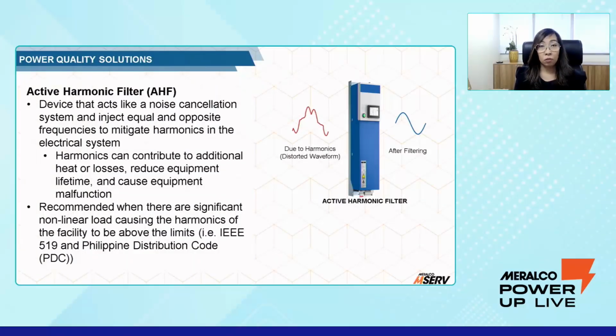So what are these solutions? First up, we have an active harmonic filter. This is by ComSys, the world's leading active harmonic filter manufacturer. It acts like a noise cancellation system which injects equal and opposite frequencies to mitigate harmonics found within your system. After filtering, you'll see the sine wave on the right, so it's much smoother. And this is recommended when there are significant nonlinear loads causing harmonics.